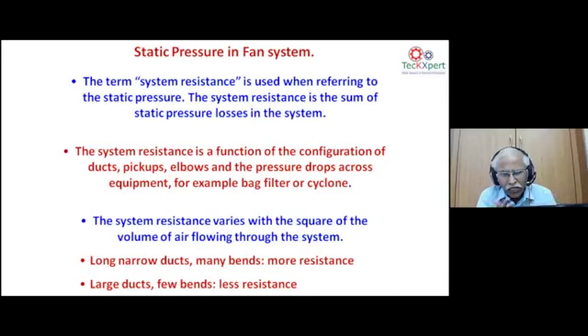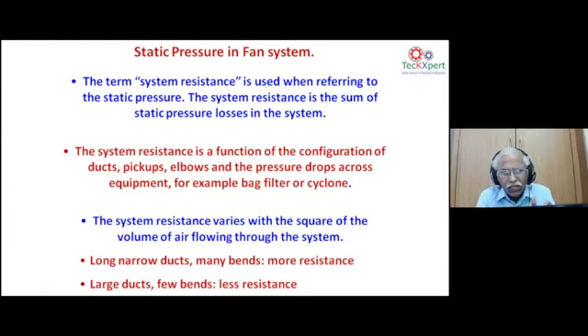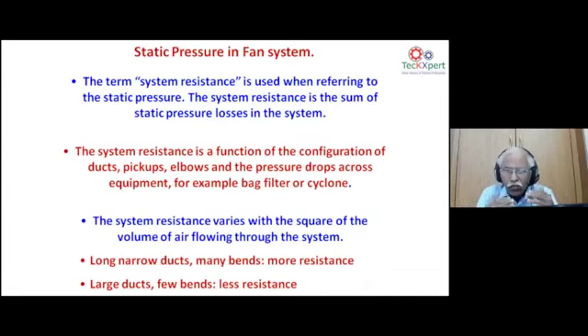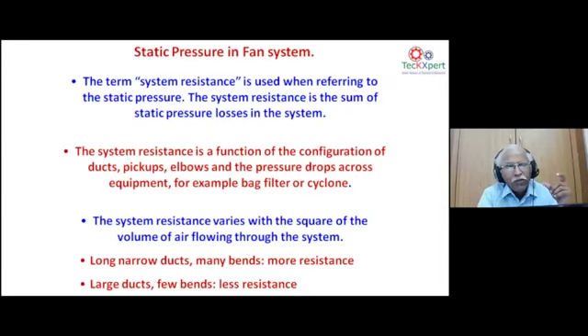System resistance is the sum of static pressure losses: duct configuration, duct size and length, pickups, elbows, and pressure drops across equipment. More elbows and pickups mean more pressure drop. Open and clean ducts from the reverse end periodically — this cleaning alone reduces system resistance. System resistance varies with the square of airflow volume — higher system resistance automatically reduces volume flow. Longer, narrower ducts with many bends mean more resistance; larger ducts with fewer bends and appropriate MOC (material of construction) reduce resistance.